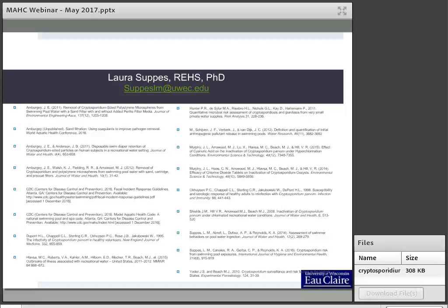And Jason, this is Michelle, just to chime in a little bit. With diarrheal incidents in smaller aquatic venues like hot tubs and spas, if there is a diarrheal incident in these smaller venues, an alternative to option 2 hyperchlorination would be draining and cleaning. As Laura pointed out in her talk, it costs money to hire somebody to hyperchlorinate for 13 hours plus. There's that time to bring the chlorine up and the chlorine down. So it might just be easier for a smaller aquatic venue to drain and clean.